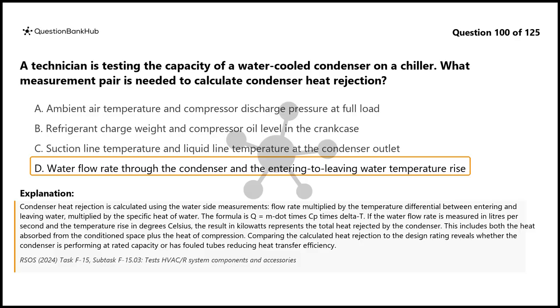If the water flow rate is measured in liters per second and the temperature rise in degrees Celsius, the result in kilowatts represents the total heat rejected by the condenser. This includes both the heat absorbed from the conditioned space plus the heat of compression. Comparing the calculated heat rejection to the design rating reveals whether the condenser is performing at rated capacity or has fouled tubes, reducing heat transfer efficiency.